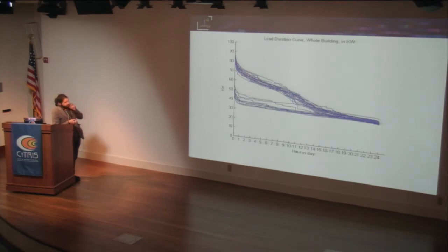And so this indicates that only for about 2 hours a day, on average, for most days, we're drawing more than 70 kilowatts. If we can knock that off by shifting loads, then we will be having a 70 kilowatt cap on our power use throughout the day in terms of demand response respective to plugs.